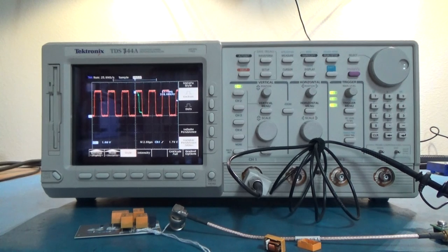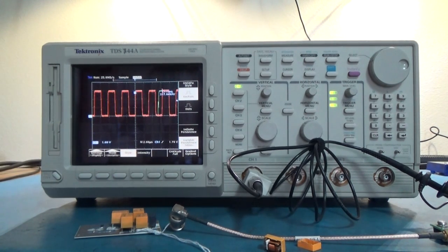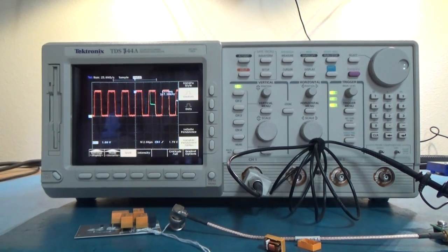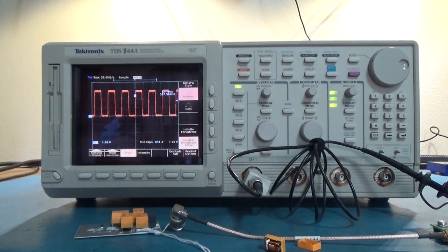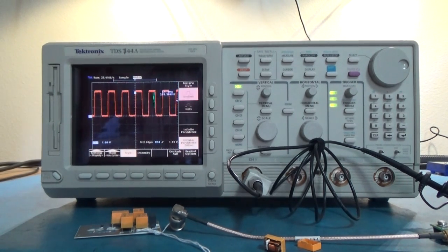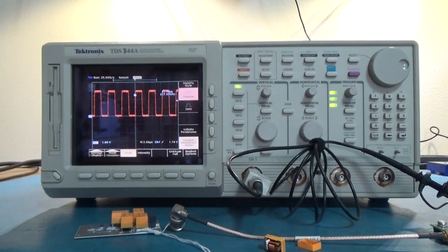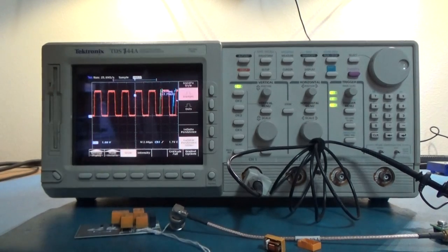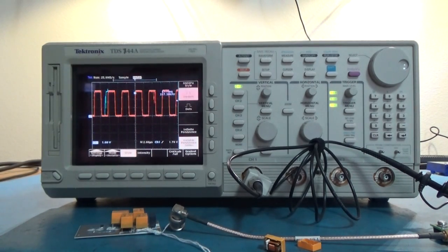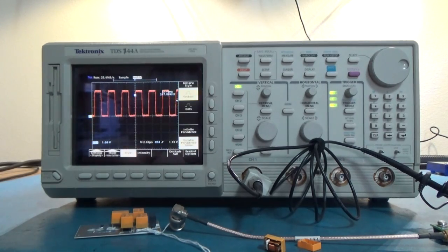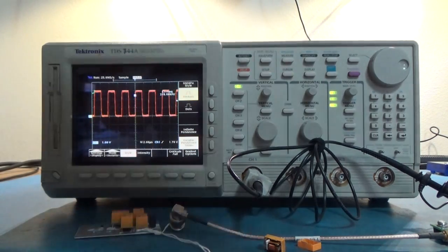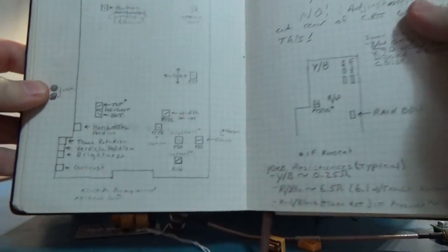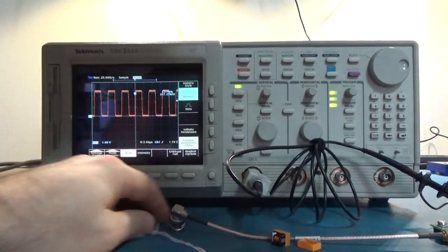When you have this plugged in, the scope's talking to you. You're doing SPC and the channel's failing. It's saying, hey, channel 2 isn't doing its duty or something. SPC information, keep in mind that the signal path compensation is affecting all channels at the same time. So a bad attenuator can cause all of your different attenuators to appear to be bad.